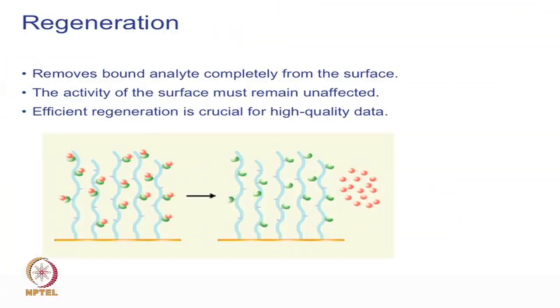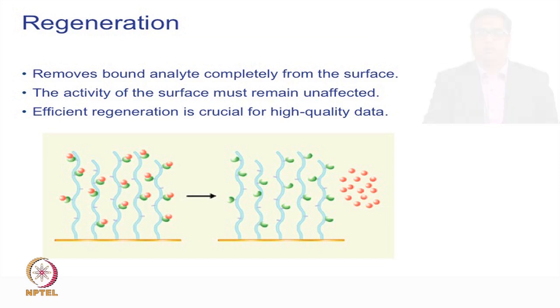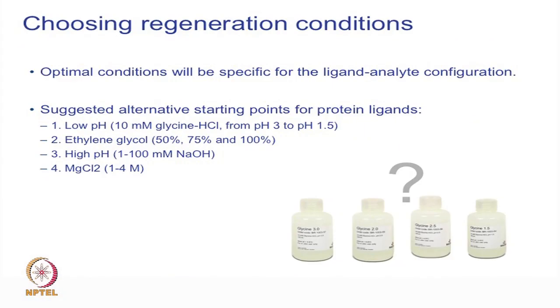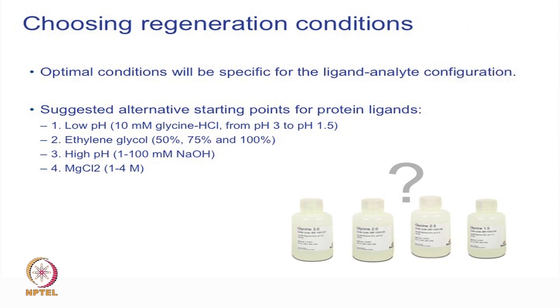Regeneration removes the bound analyte completely from the surface. The activity of the surface must remain unaffected after regeneration, and an efficient regeneration is crucial for high quality data. We need to test the regeneration surface - we can do regeneration scouting before starting an assay to identify the appropriate regeneration conditions. Common regeneration conditions include low pH, ethylene glycol, high pH, and magnesium chloride.